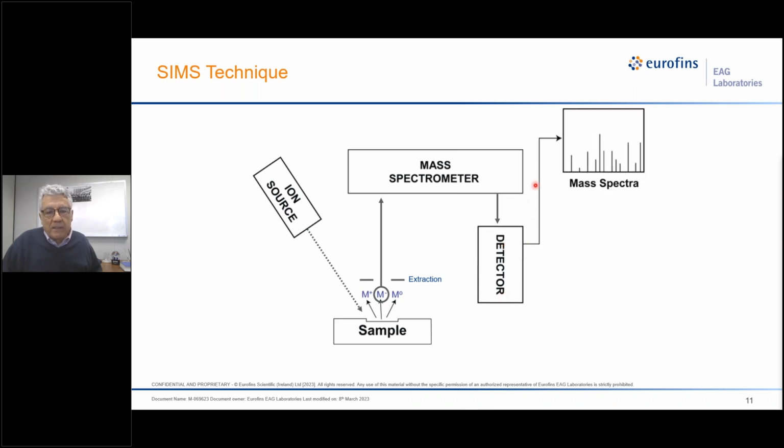The schematic of the instrument is that you have the primary ion beam hitting the sample, and it's rastered in a certain square fashion. And then as this sputtering continues, the surface recedes into the bulk, and the particles that existed at the very top of the surface will get ejected in the form of neutrals, negative ions, or positive ions.